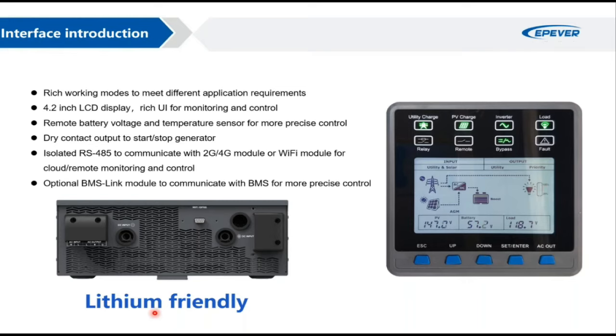UPOWER HI can be connected to a lithium battery, which usually comes with a Battery Management System, or BMS. BMS protects the battery, for example, from overcharging, over discharging, or charging in extreme temperatures, and so on. So UPHI is compatible with BMS for lithium batteries via Modbus. For example, it reads the battery voltage directly from the BMS. This is very common in battery brands like PylonTech, Meritson, Narada, Foxes, and a lot of modern lithium batteries.